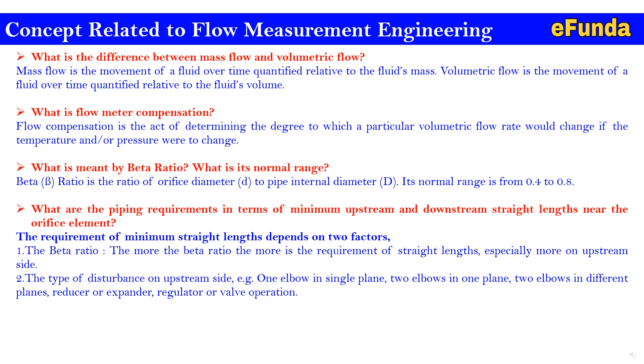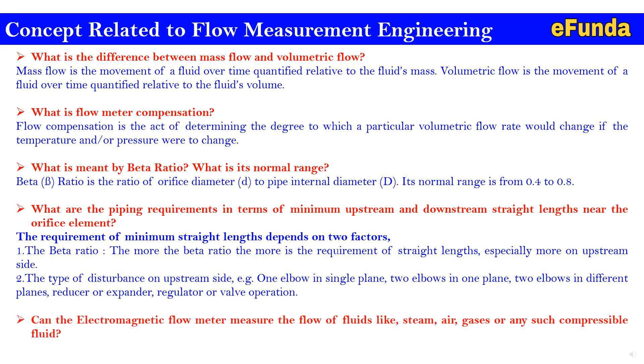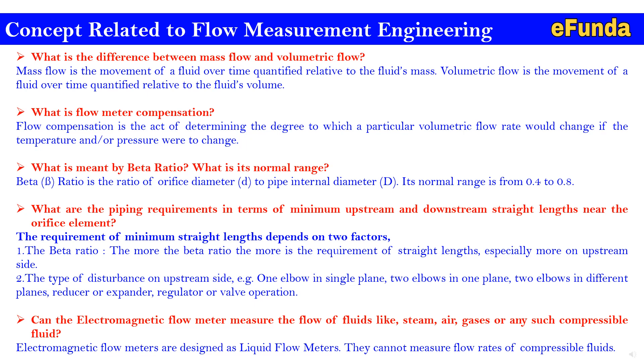These disturbances increase the upstream length requirement so as to have settled flow and get a correct reading across the orifice plate. Can an electromagnetic flow meter measure the flow of fluids like steam, air, or other compressible fluids? Electromagnetic flow meters are designed as liquid flow meters — they cannot measure flow rates of compressible fluids. This covers the typical concepts related to flow measurement.